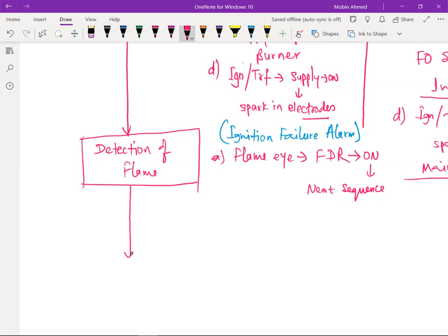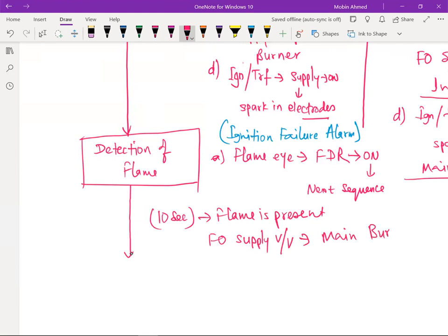So now, detection of flame, suppose for 10 seconds flame is available. Flame is present. In that case, now the FO supply valve will energize, and the main burner is going to have the FO. At the same time, the FO bypass valve will close. Let me write here, open and close. So this is going to open and this is going to close. So the main burner is going to have the FO, and circulation will stop. No circulation. So this is what is going to happen.